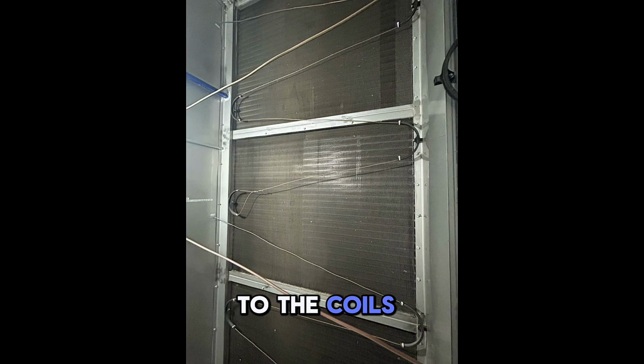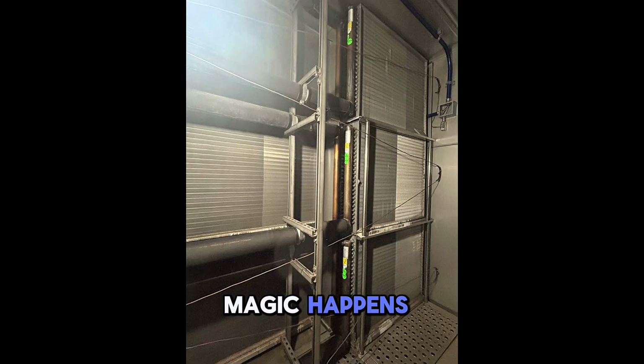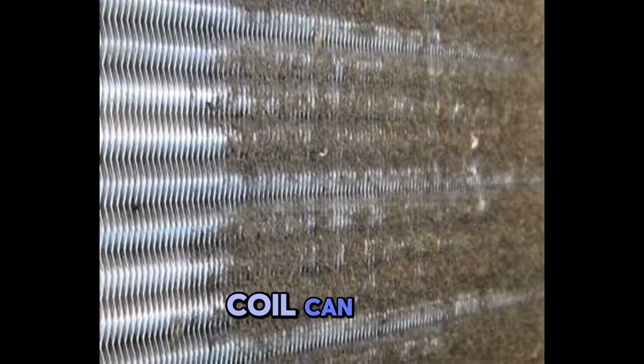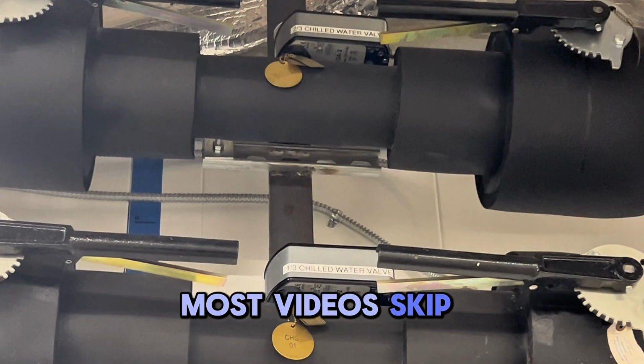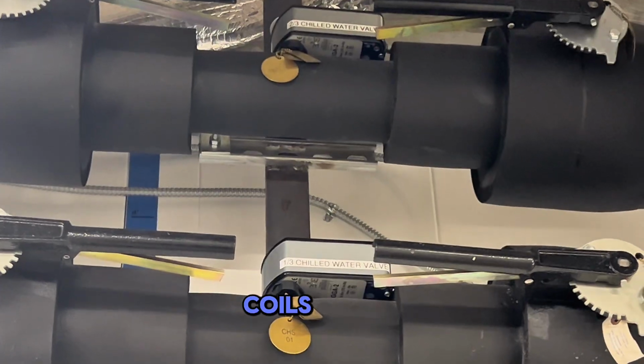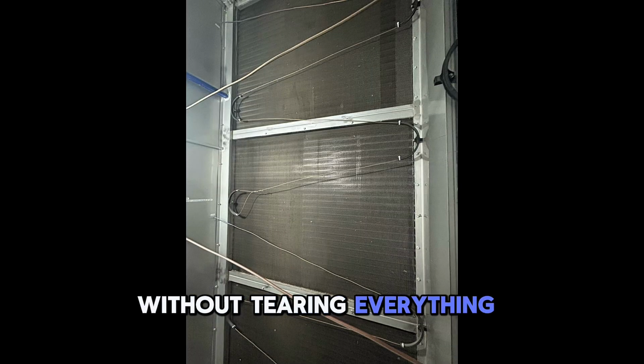Now we get to the coils, where the real magic happens. Hot water and chilled water runs through these fins and conditions the air. One dirty coil can cut efficiency in half. I'm going to show you something most videos skip: how to quickly tell if your coils are a problem without tearing everything apart.